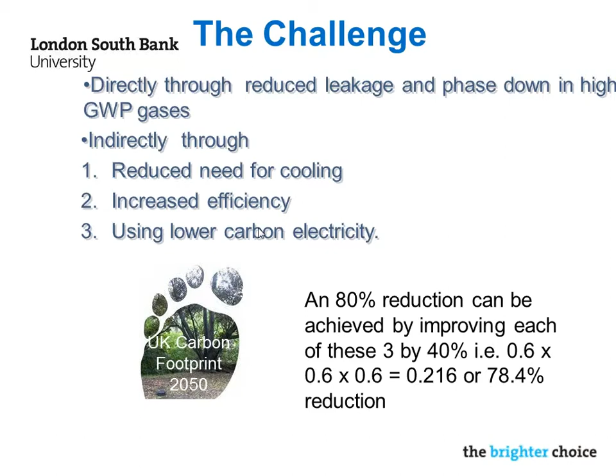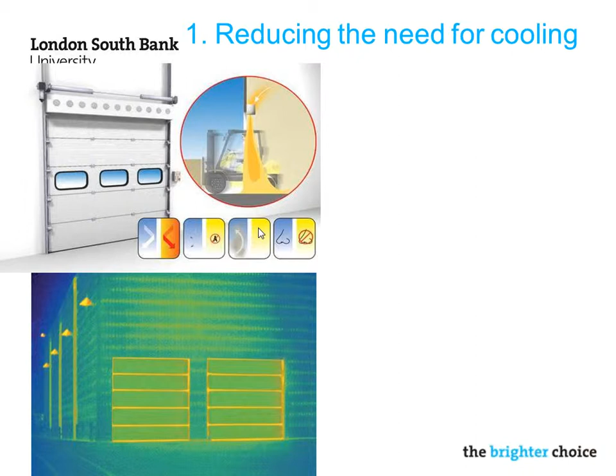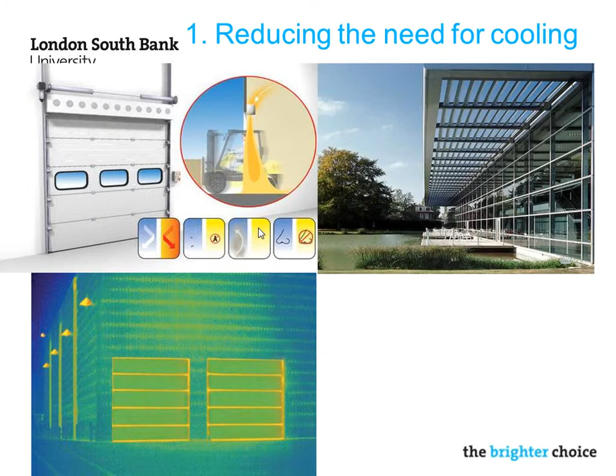So how would I reduce the need for cooling? If I had a building, or this is a cold store, I would close the door and let the cold stay in. Or we would make sure the insulation is the appropriate thickness and that it works. This is a thermography picture showing a cold store, showing some cold bridging.